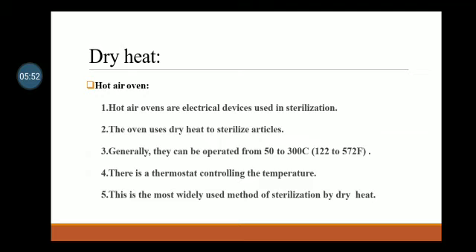First, dry heat. Hot air oven. Hot air ovens are electrical devices used in sterilization. The oven uses dry heat to sterilize articles. Generally, they can be operated from 50 to 300 degrees Celsius, that is 122 to 572 Fahrenheit. There is a thermostat controlling the temperature. This is the most widely used method of sterilization by dry heat.